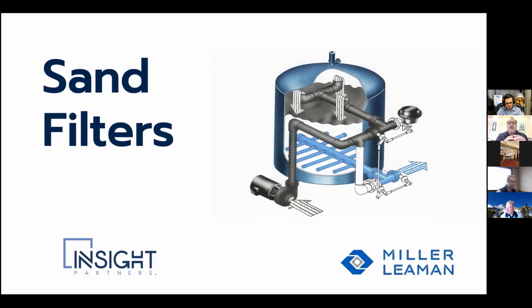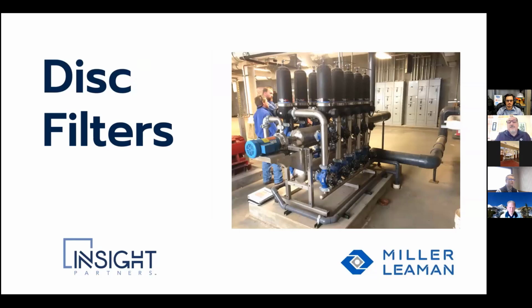The problem is if you have a lot of, say, calcium carbonate or anything like that in your water, or the water's hard, that bed of sand will start hardening. It'll become hard, basically, and the water then starts channeling. So your micron level will ultimately start going up a little bit. And we do sell sand filters. We sell quite a few, with sizes all the way from 12-inch up to a 48-inch. We've also made some 56-inch if you need larger. But again, there's a lot of water compared to a disc filter. And if you're using your cooling tower water for that, then you're flushing out your chemicals as well. The next one is the disc filtration technology.